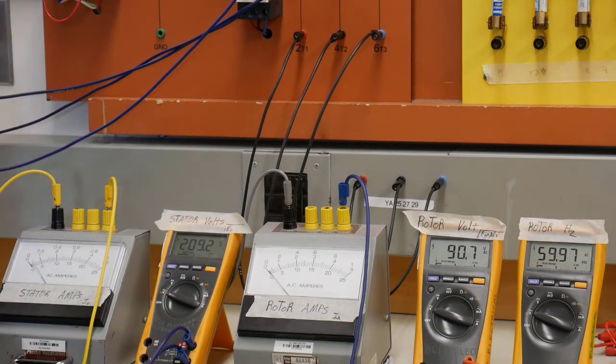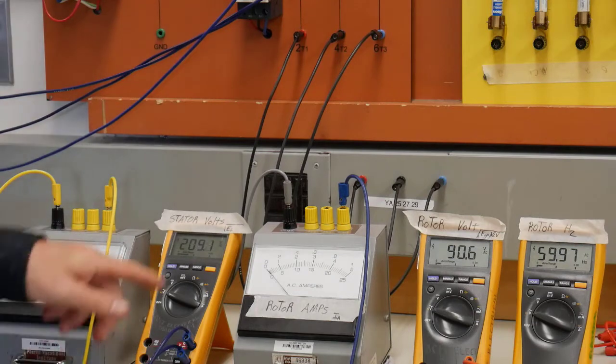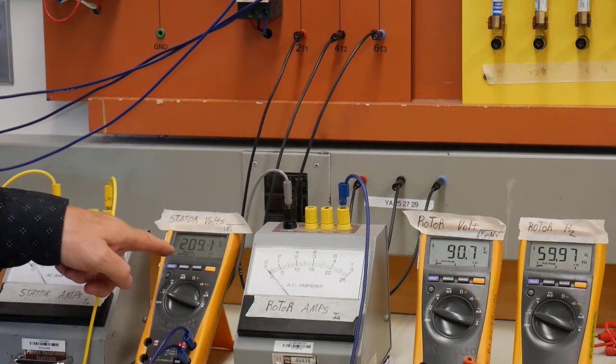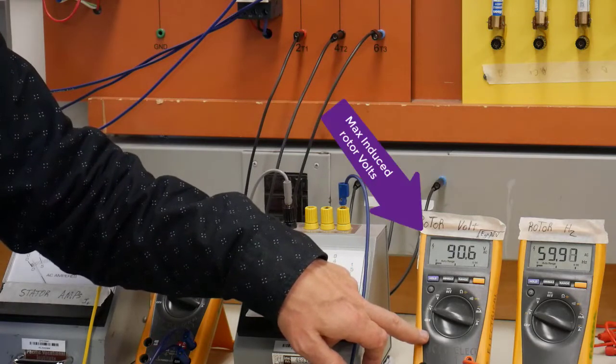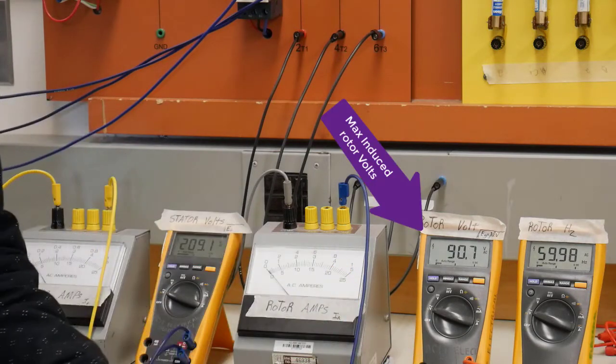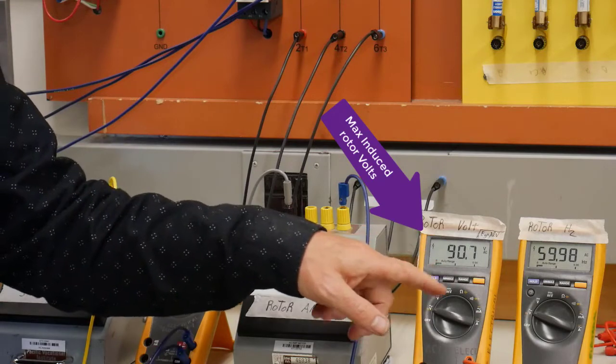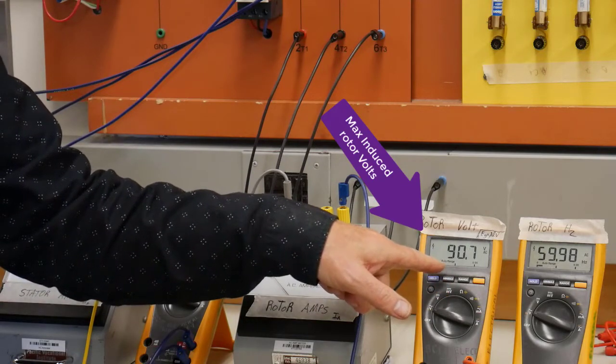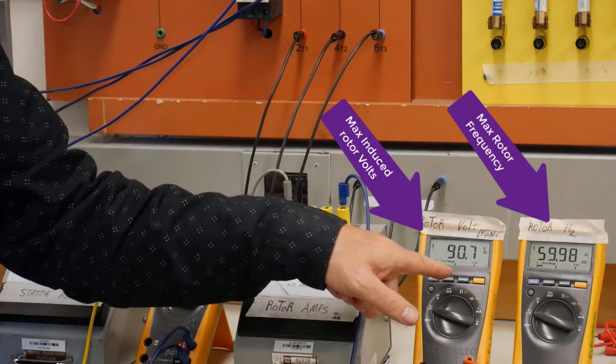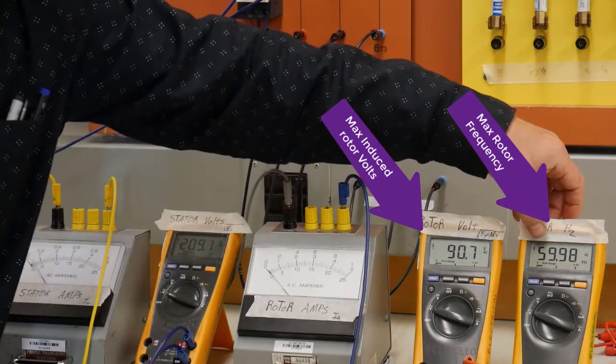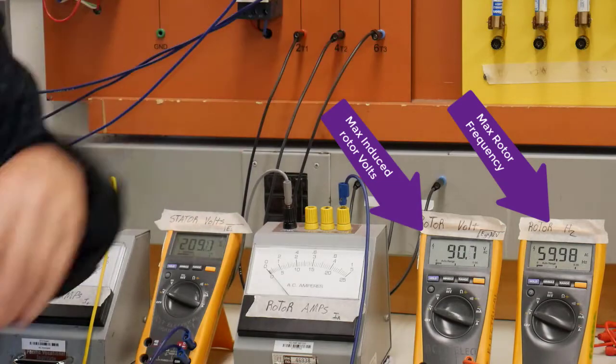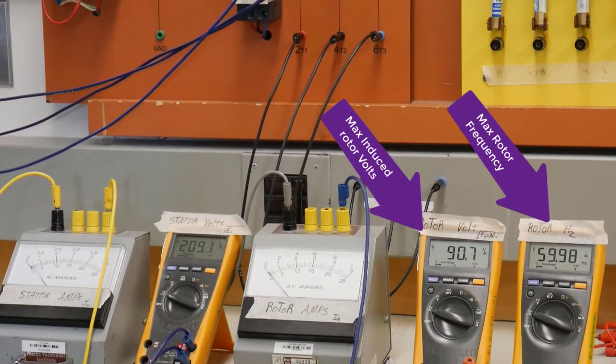The main contactor supplying power to the stator is energized. We've got 209 volts. Our rotor, because there's no closed circuit and it's not rotating, acts as a transformer with 90 volts across the rotor lines and the frequency is the same as supply frequency: 59.98, essentially 60 hertz.